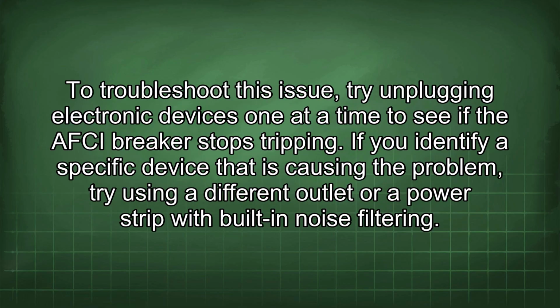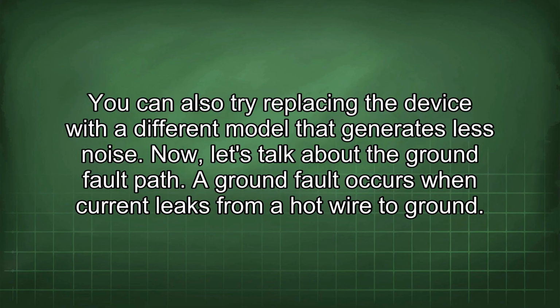To troubleshoot this issue, try unplugging electronic devices one at a time to see if the AFCI breaker stops tripping. If you identify a specific device that is causing the problem, try using a different outlet or power strip with built-in noise filtering. You can also try replacing the device with a different model that generates less noise. Now, let's talk about the ground fault path.